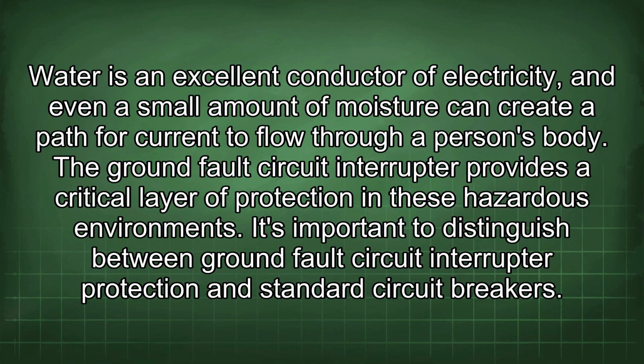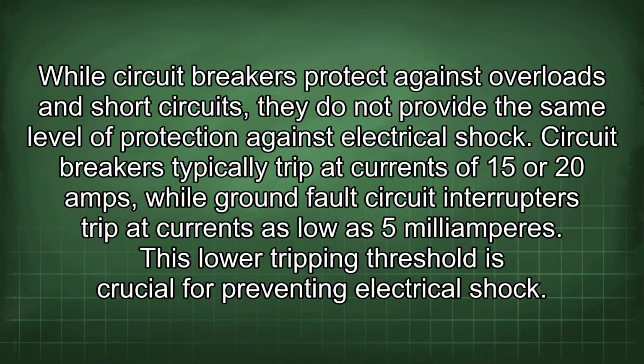It's important to distinguish between ground fault circuit interrupter protection and standard circuit breakers. While circuit breakers protect against overloads and short circuits, they do not provide the same level of protection against electrical shock. Circuit breakers typically trip at currents of 15 or 20 amps, while ground fault circuit interrupters trip at currents as low as 5 milliamperes. This lower tripping threshold is crucial for preventing electrical shock.